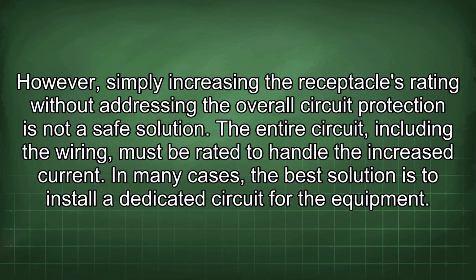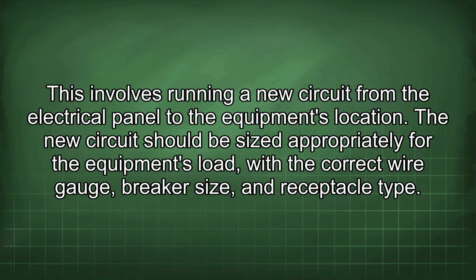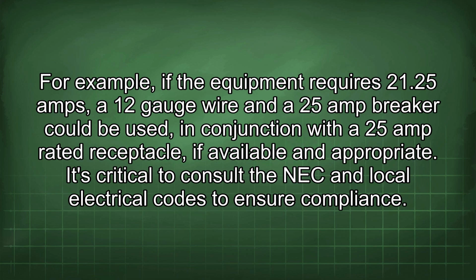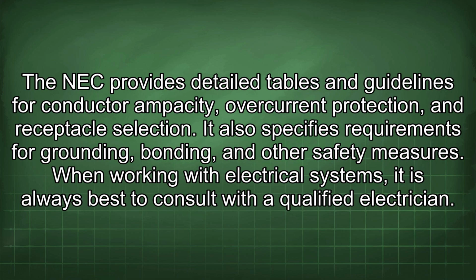In many cases, the best solution is to install a dedicated circuit for the equipment. This involves running a new circuit from the electrical panel to the equipment's location. The new circuit should be sized appropriately for the equipment's load, with the correct wire gauge, breaker size, and receptacle type. For example, if the equipment requires 21.25 amps, a 12-gauge wire and a 25 amp breaker could be used, in conjunction with the 25 amp rated receptacle, if available and appropriate. It's critical to consult the NEC and local electrical codes to ensure compliance. The NEC provides detailed tables and guidelines for conductor ampacity, overcurrent protection, and receptacle selection.